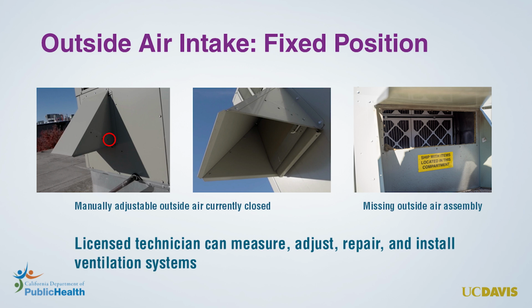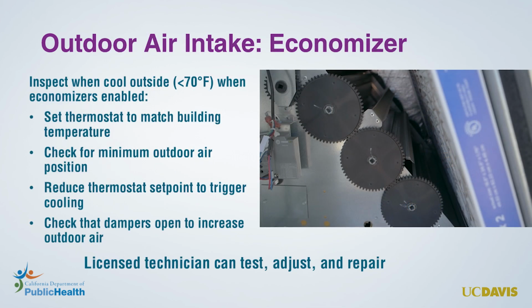Document any fixed position outdoor air intakes that appear to be set incorrectly, missing, or allow no outdoor air at all. A licensed technician can measure outdoor air rates, adjust and repair systems, and modify existing systems to add outdoor air. Another very common type of ventilation system is an economizer.